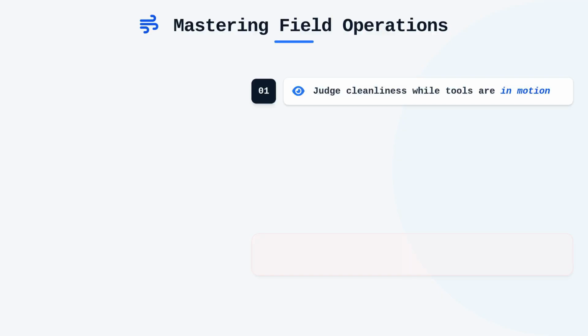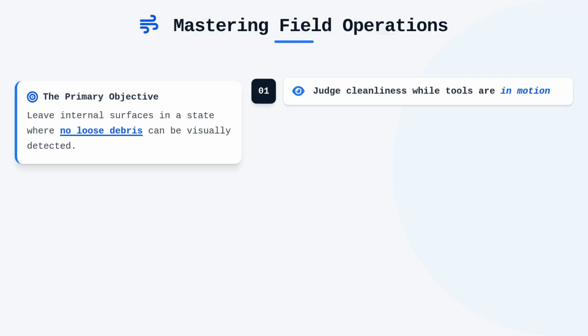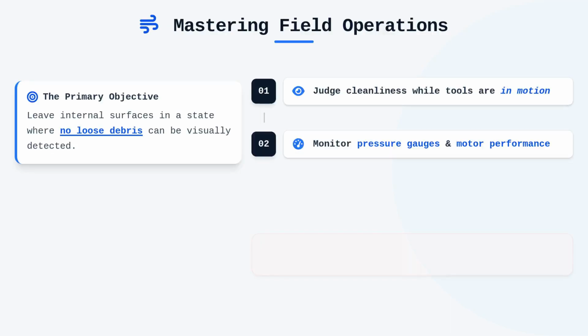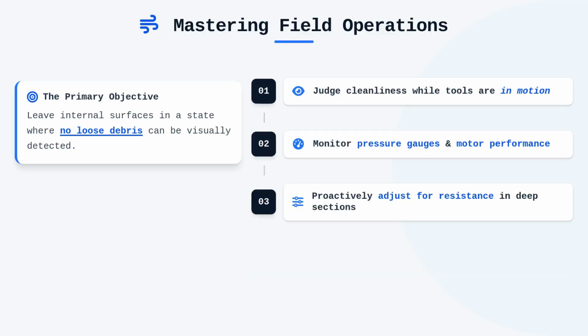Ultimately, successful field operations depend on your ability to judge the cleanliness of the ductwork while the tools are in motion. You should approach every project with the mindset that the goal is to leave the internal surfaces of the HVAC system in a state where no loose debris can be visually detected. By monitoring your air pressure gauges and listening to the performance of your electric or pneumatic motors, you can proactively adjust for resistance as the tools move through deeper sections of the ductwork.